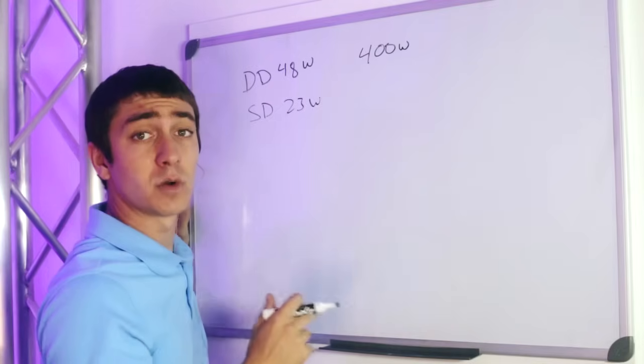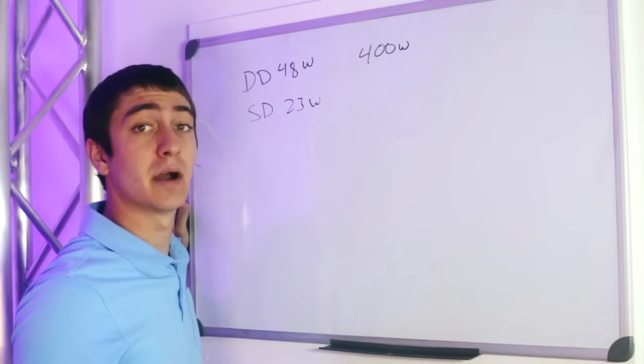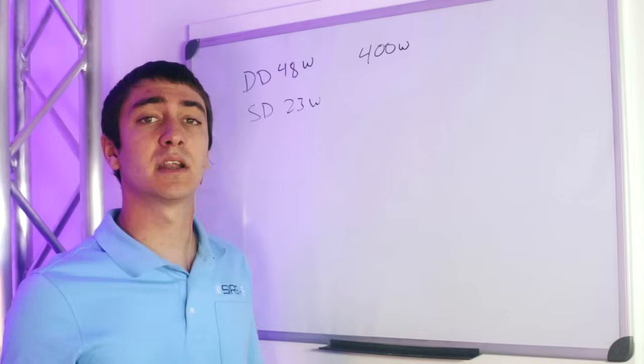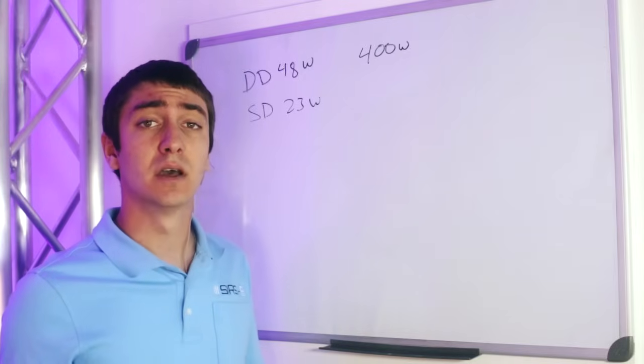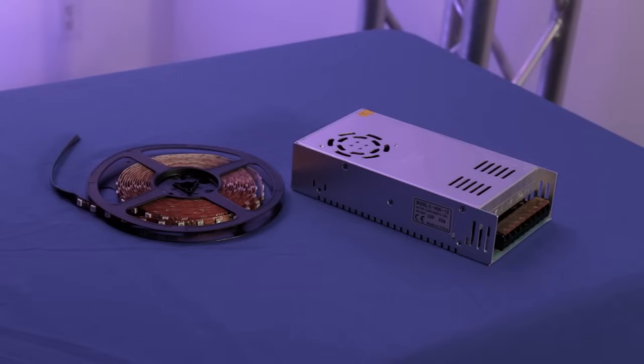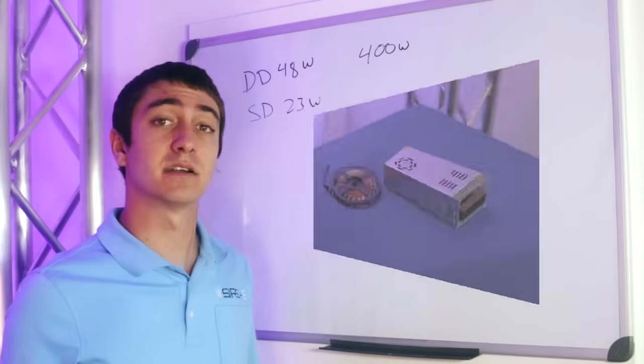And this right here, the 400 watts, that is the capacity of the power supply. But you never want to run a power supply at full capacity, because what you run risk of is getting it too hot and that will shorten the life of your power supply, not to mention other issues that could arise from that.